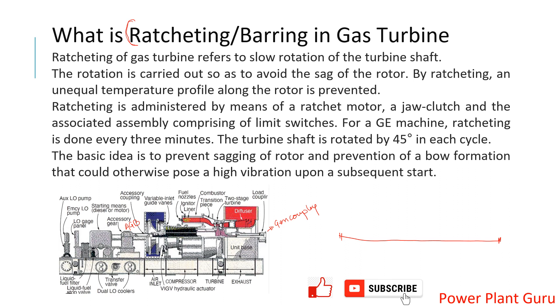If I shut down the machine and keep this shaft stationary, the normal tendency is that because this shaft is very long, it will have a tendency to bow down or sag because of its weight and center of gravity. Although it will have this tendency even when cold, after shutdown it is hot, and this sagging tendency is much higher when it is hot — because of the metal properties.